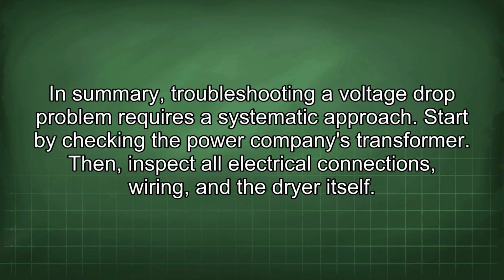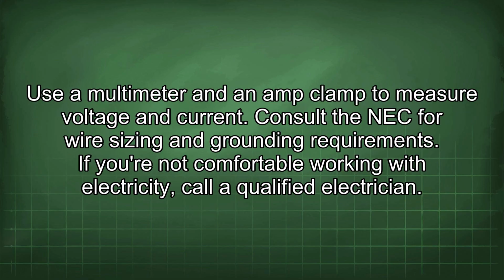In summary, troubleshooting a voltage drop problem requires a systematic approach. Start by checking the power company's transformer. Then inspect all electrical connections, wiring, and the dryer itself. Use a multimeter and an amp clamp to measure voltage and current. Consult the NEC for wire sizing and grounding requirements. If you're not comfortable working with electricity, call a qualified electrician.